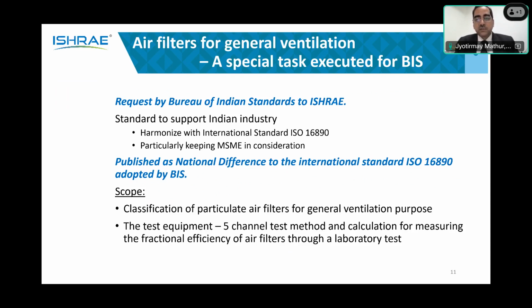So what we did was set up a task force for fractional testing, efficiency testing of filters. We found that the 12-channel sampler based testing facility required per ISO standard was quite costly. So for the short term, we tried and developed an alternate method using a 5-channel sampler. Through a statistical method, by getting filters tested in both settings, we developed an equation, and through that equation we created an alternate compliance path—a national difference, you could say in ISO terms—for India, for a short period.